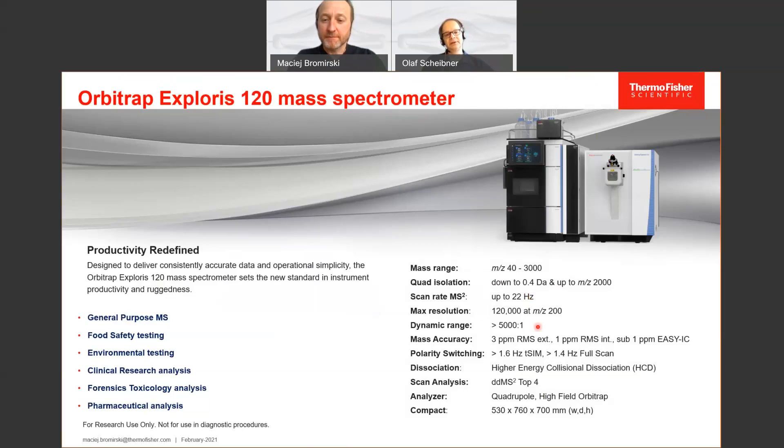Mass accuracy — as some of you may be used to from the Q Exactive series — is the same here: better than 3 ppm without internal calibration. With the standard internal calibration, taking one background signal as a calibrant, you have 1 ppm mass accuracy. And if you use the newly introduced EASY-IC internal calibration, you have mass accuracy better than 1 ppm over a course of at least 5 days.